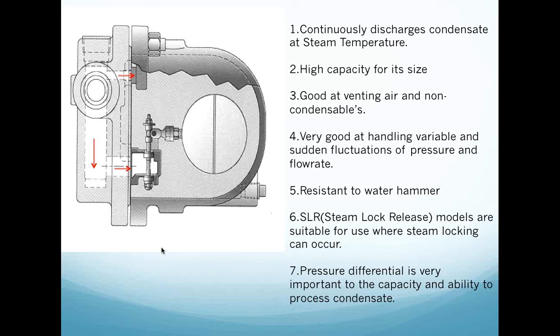Now, I didn't say that gave you the pressure to actually put that condensate into that return header, because I don't know what that return header pressure is. So you're going to have enough pressure, number one, to get it up to the elevation that you have to get it to, but number two, to actually get it into that envelope or that space. Whatever that pressure is, you're going to have to overcome to get that condensate into it. But remember, you can lift condensate 2 feet for every 1 pound of pressure that you have to help push it up the elevation you want to climb to get it into that receiver or the condensate return header.